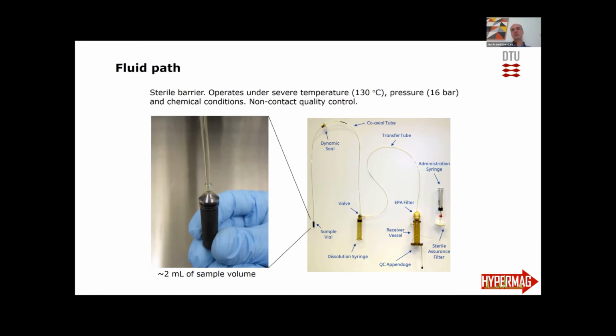Here, there's no chemistry involved, but still, this was the idea that was adopted, to use these disposable cassettes. It's a little complicated and expensive for a disposable, but it does serve the basic purpose. It can be loaded in the pharmacy in a clean room under sterile, aseptic conditions, and then the sterility is maintained into the polarizer and throughout the process until it's released and injected into the patient.